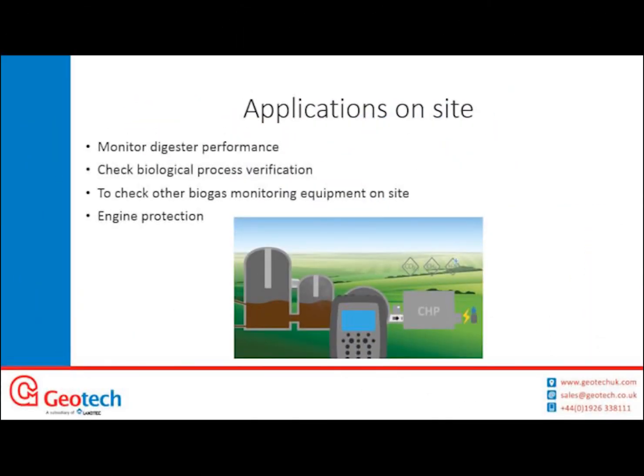So why would you use a Biogas 5000? The first main application is to monitor digester performance. The digester produces both a liquid phase and a gas phase, and the Biogas 5000 monitors the gas phase. From this you can gauge how well your biological process is working, see how calorific the gas you're producing is, and make sure the process is not going sour or producing unusable gas.